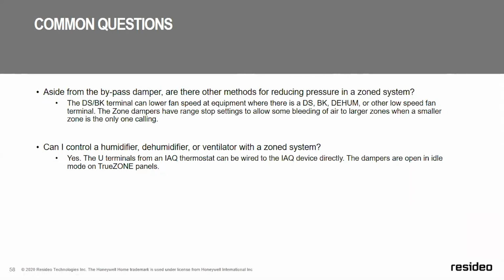Yep. Aside from bypass damper, are there other methods of reducing pressure in a zone system? Well, as we covered on a previous slide, you can use the DSBK terminal to lower the fan speed when only one zone is calling.